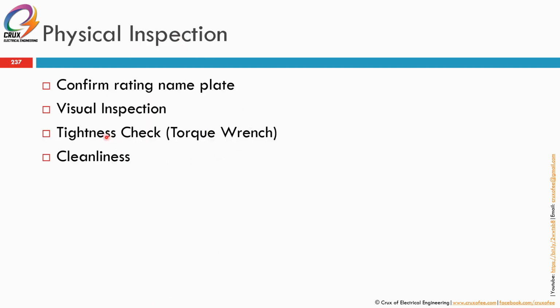So physical inspection is confirming the rating on the nameplate, visual inspection, tightness check using the torque wrench, and then a cleanliness check, making sure there's no debris, no dust, and no leftover tools left within the compartment of the terminal box, within the switchgear or the transformer terminal compartment. So these are the very basic physical inspections. Okay, and some things that you might gain only from experience are things like looking at whether the clearance and the creepage distance are enough or not.